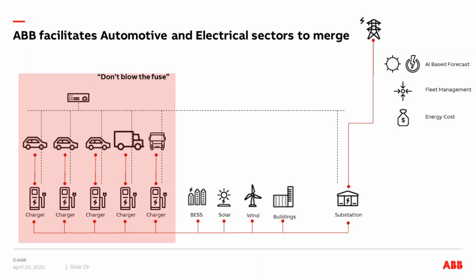This is a scenario we have installed for Europe's biggest charge point operator, installing high power fast chargers on sites beside highways where the grid connection is not sufficient. We supply a battery energy storage system in combination with the chargers, and based on the connection to a local site controller, we can derate the chargers when required to meet the grid connection, let the battery storage kick in to support the chargers, or allow the battery to charge when energy is available.